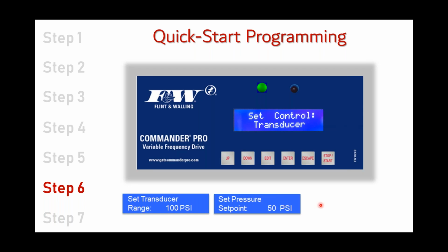And then your next submenu pops up, and this is where you set your pressure point. It's going to be factory default at 50 psi, but if you want to change that, you use your up and down buttons, and you can run it up or you can run it down. How far can you run it up? Well, the programming in a drive is going to allow you to run your pressure set point up to within 5 psi of the range of the transducer. So theoretically, you could run this all the way up to 95 psi. I'm not sure what the application would be that would warrant that, but that's the range that you have.